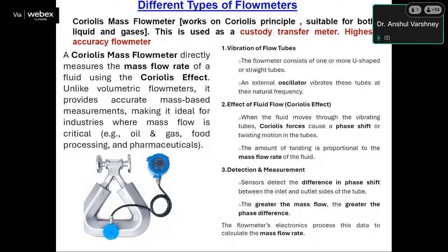At our lab, we have observed that if there is a false detection of phase shift, it will highly affect the mass flow rate result of the mass flow meter. For example, we receive multiple mass flow meters from sugar industries, and sometimes there are residues or deposition in the U-tubes of the mass flow meter. Because of this deposition, there will be a shift in the natural frequency of these vibrating tubes, and that severely affects the output of these mass flow meters.